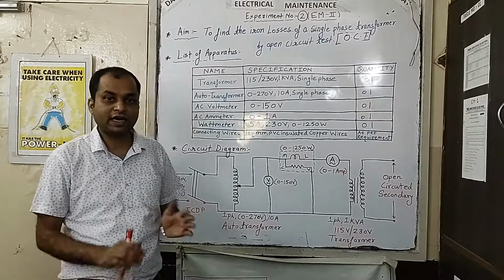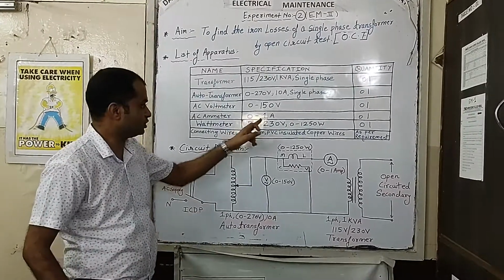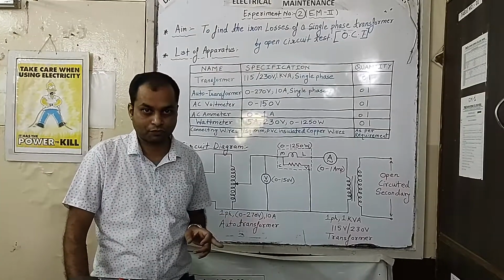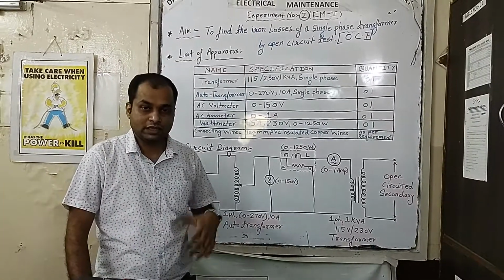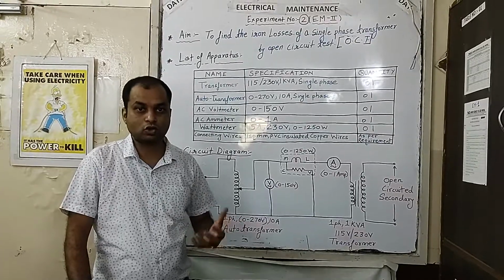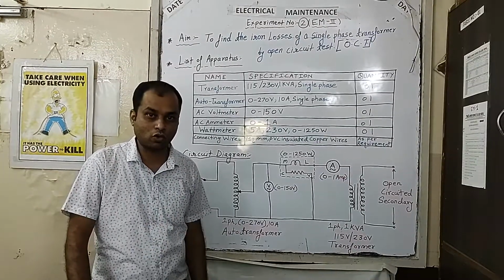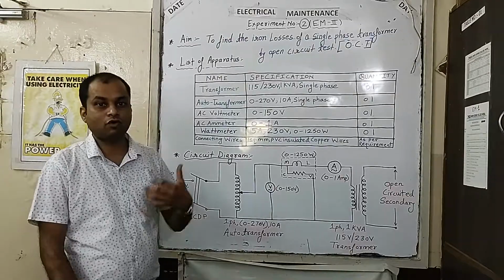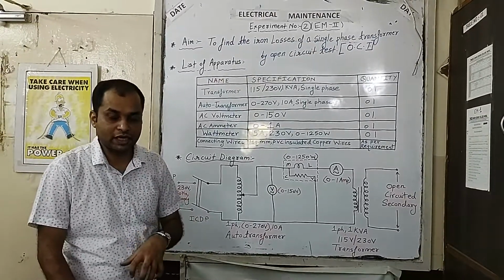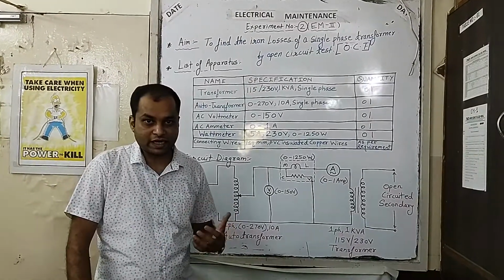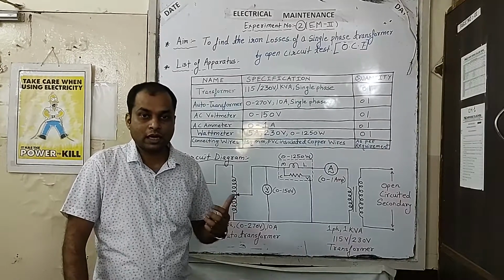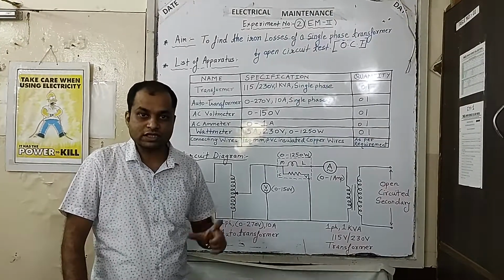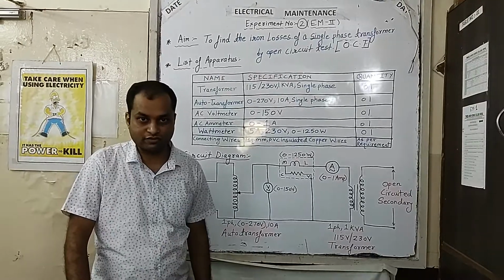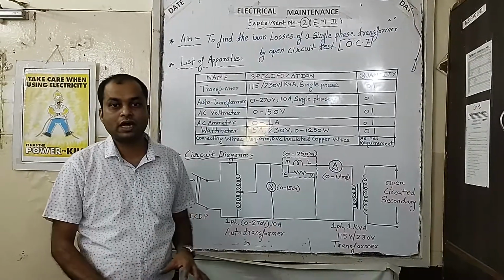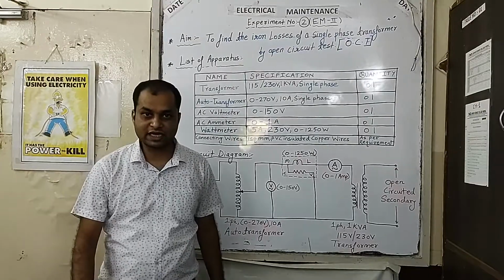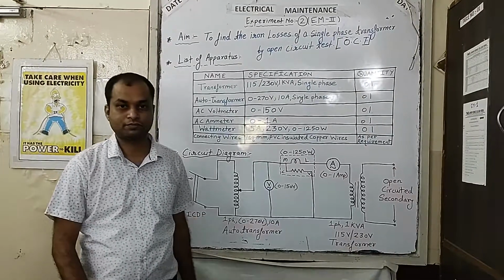As the current rating is very small, we will use a 0 to 1 range ammeter, and this current is mainly utilized to supply the losses which are taking place in the core. So whatever the wattmeter reading which we will be measuring, that will indicate the losses taking place in the core of a transformer. So let us have a look at the equipments or apparatus that we will use for the practical.